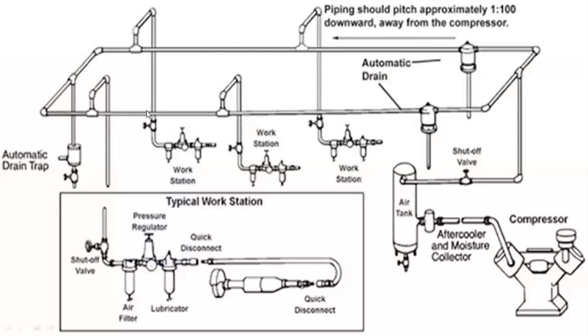This is what we call a ring main — a compressed air network running all around the plant. You have this pipeline going through the entire plant, with workstations at various points: workstation one, workstation two, workstation three, and so on. In a typical workstation, you will have a shutoff valve, air filter, lubricator, pressure regulator, and a quick connect and disconnect. This can be connected to a grinder, drilling bit, screwdriver, or any pneumatic tool.